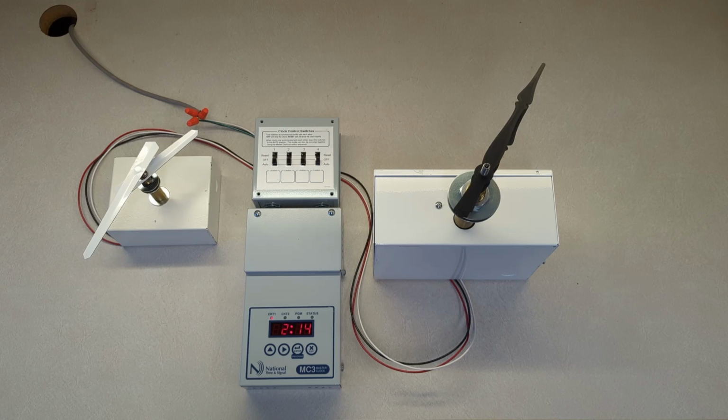To enter the Set Time and Date menu on the MC3, press and hold the Program button for 5 to 10 seconds. If you get to a menu that looks like this, you held the Program button for too long and you are now in the Tech menu. You will need to go back to the main display and start over. To return to the main display, press the Exit button.